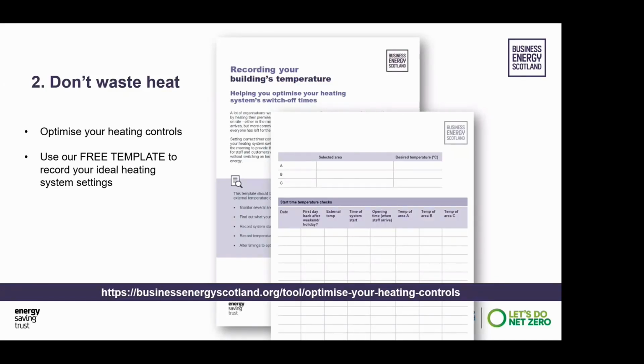Now, buildings and their content store heat, and most buildings will stay warm for long after the heating has been switched off. Yet many organisations leave it switched on and powered up all the way until the end of the day when staff are going home. This can be changed by appropriate use of timers and controls, for instance, setting the heating to switch on prior to staff arriving, so there's an ambient temperature at the start of the day, and it'll also reduce instances of staff manually adjusting that thermostat on arrival just to speed up the heating a bit. Correct timer controls will also mean that your system switches off at a time that will ensure desired temperatures are maintained to the end of the working day, without the office being heated after everybody's left.